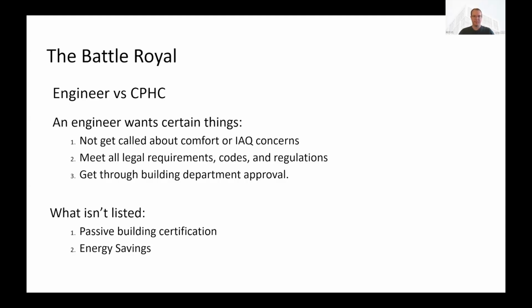What they're not necessarily interested in is passive building certification compliance or energy savings. Tangentially, maybe they are, but I think that's a secondary concern to some of these at the beginning. So what we often see is higher airflow rates, just to make sure that you're meeting all the requirements and getting through the building department approval and those sorts of things. But the higher or conservative airflow rates we'll see coming up may cause some problems on meeting certification targets or energy savings.